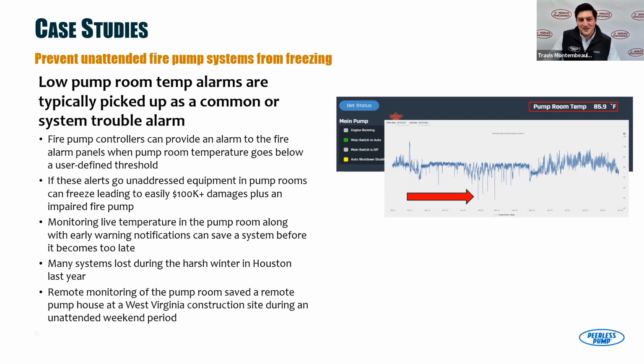This specific site was an unmonitored construction site over a holiday weekend, and this fire pump house was providing temporary fire protection for the construction site. It was a winter day with gusting winds, and the doors to the pump house blew open. The site leader, who was home on a Saturday, gets a text message saying your pump room is down to 40 degrees Fahrenheit. So he gets in his truck, drives on site, realizes the doors are open and the heater couldn't keep up in the pump room. He closes the doors, the temp rises, and he saves the system, because we all know freezing temperatures are just not good for fire pump systems.